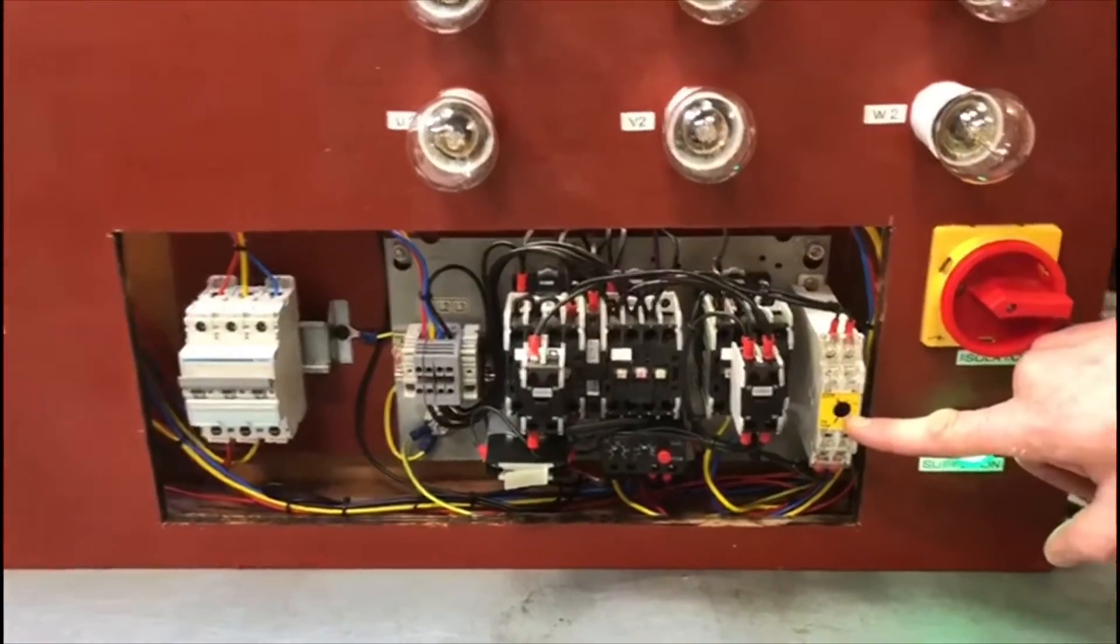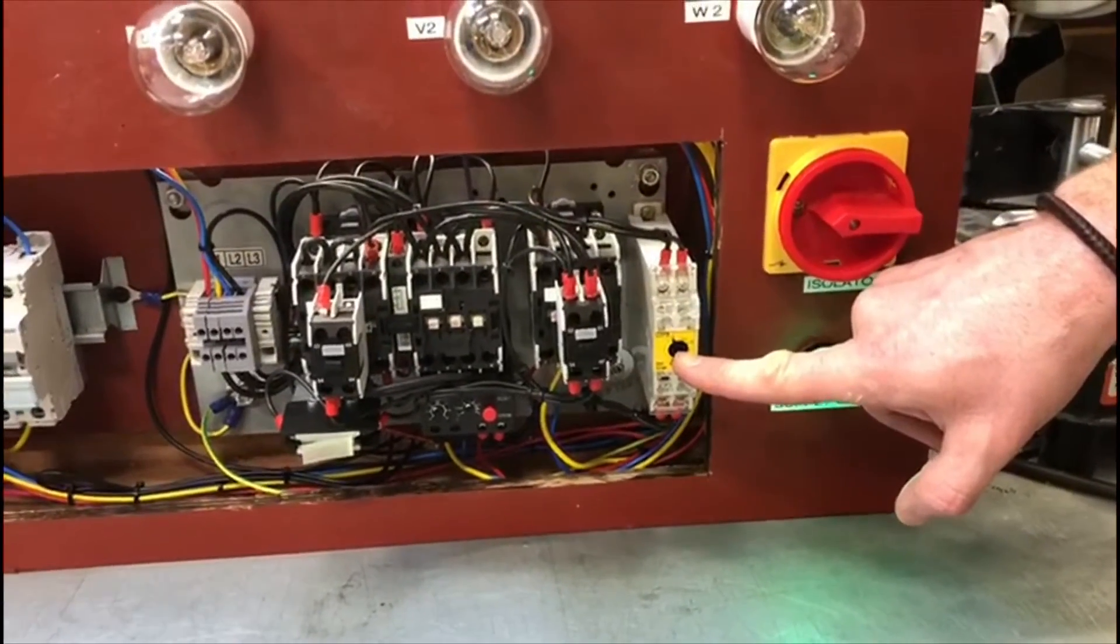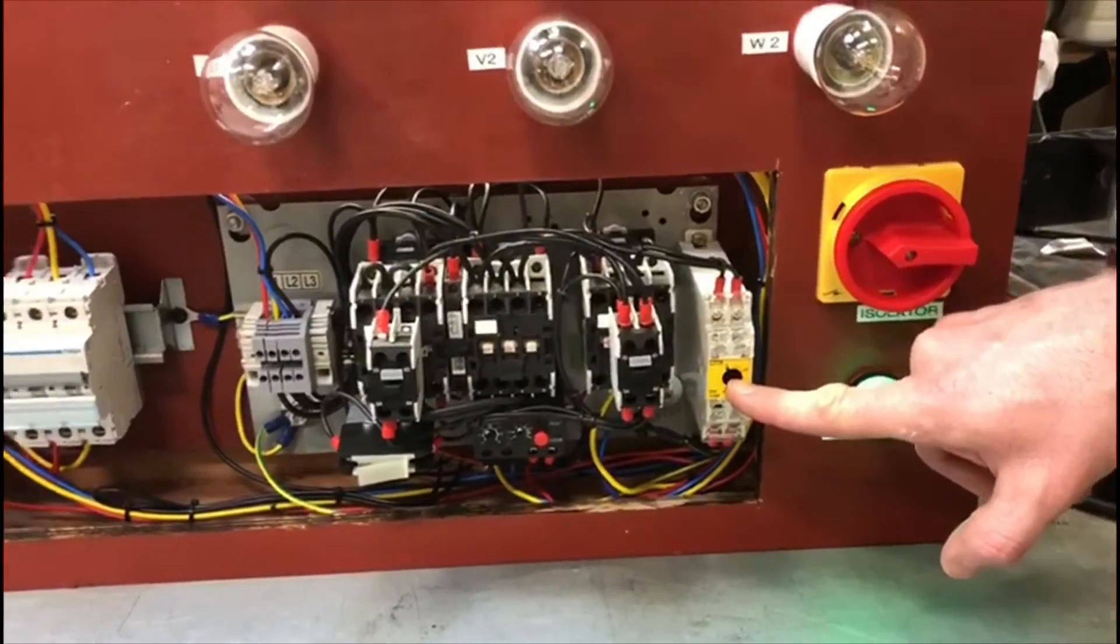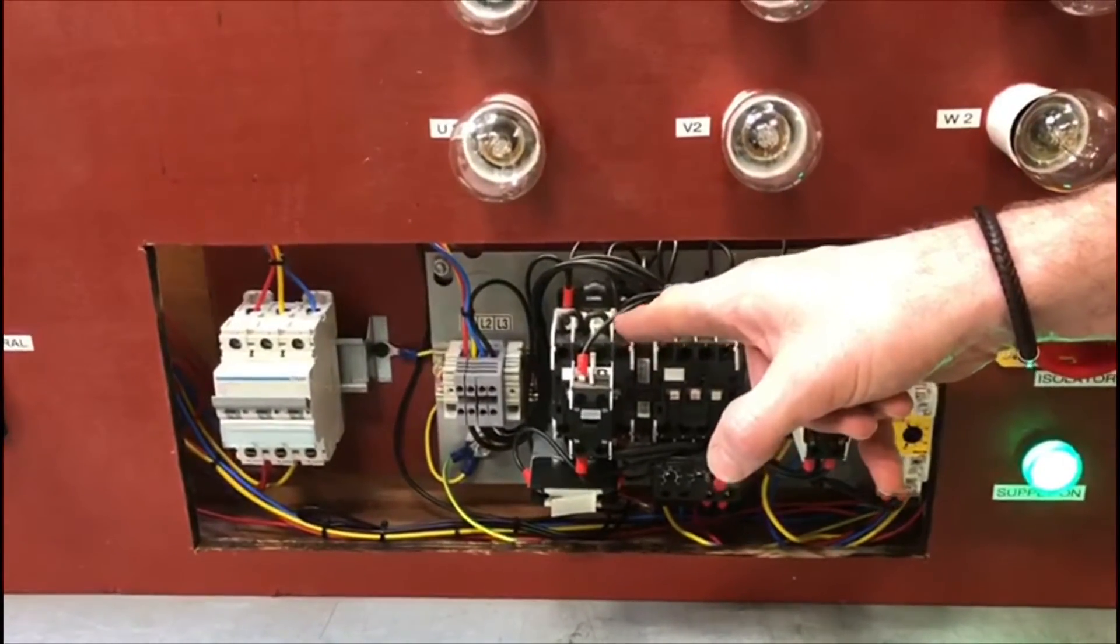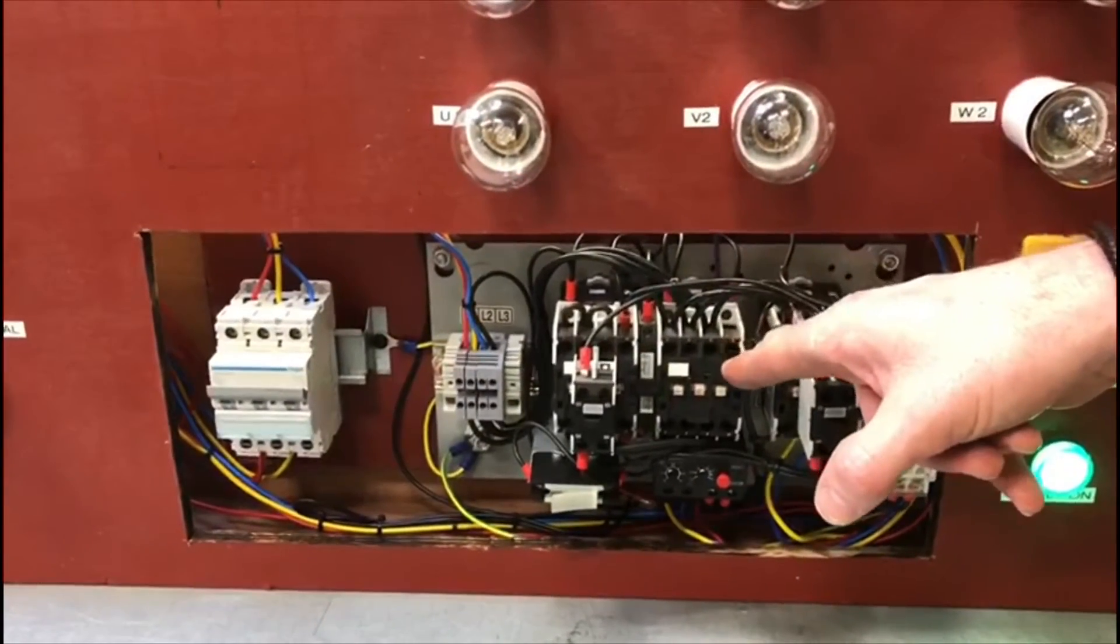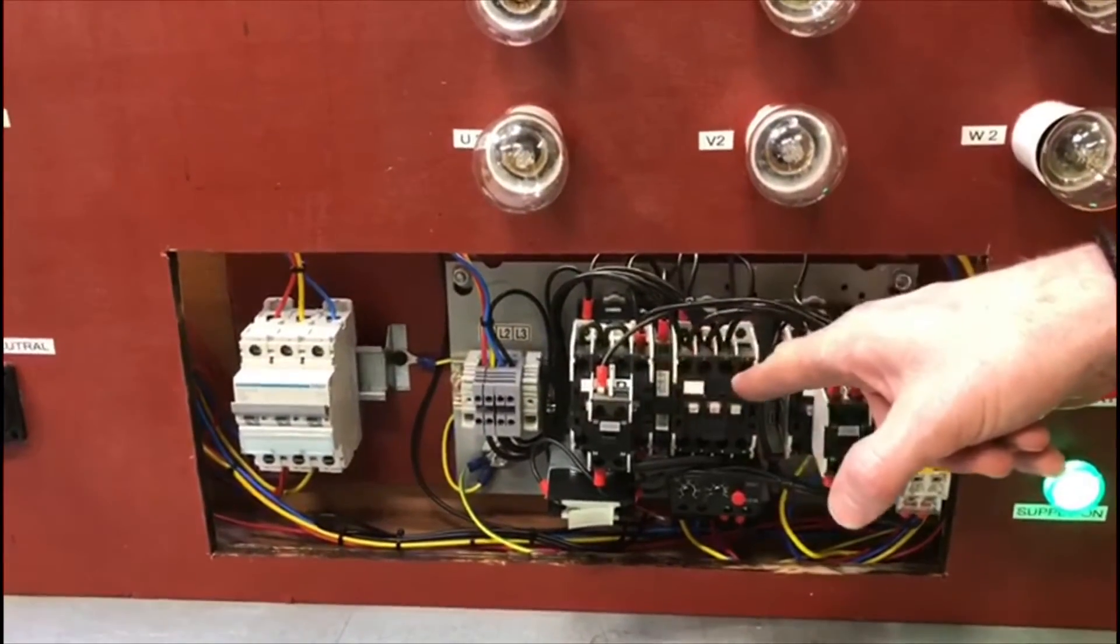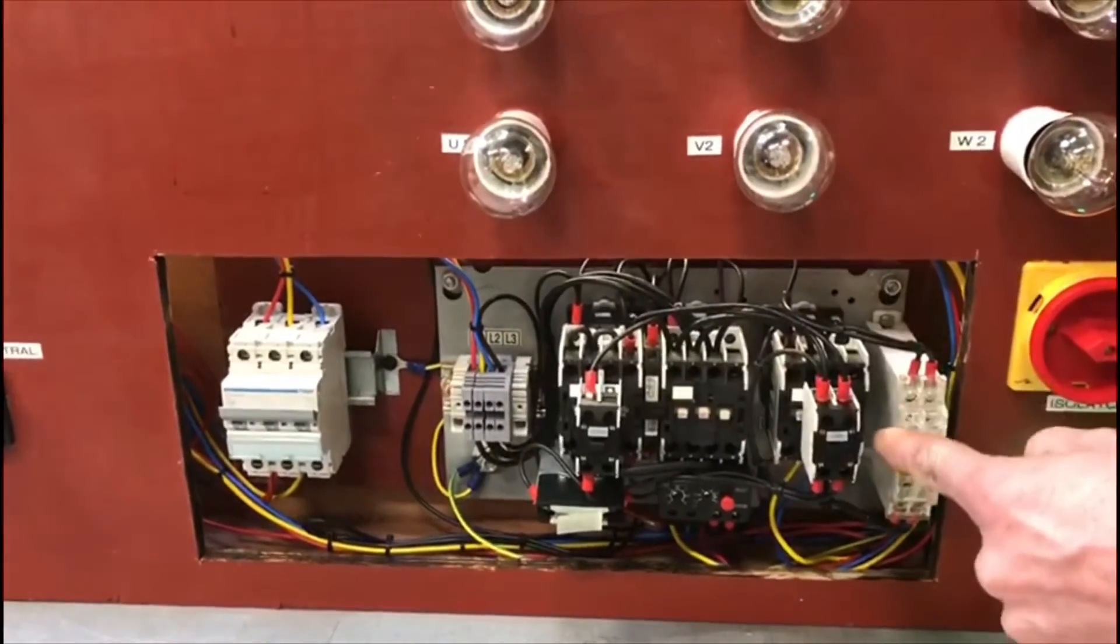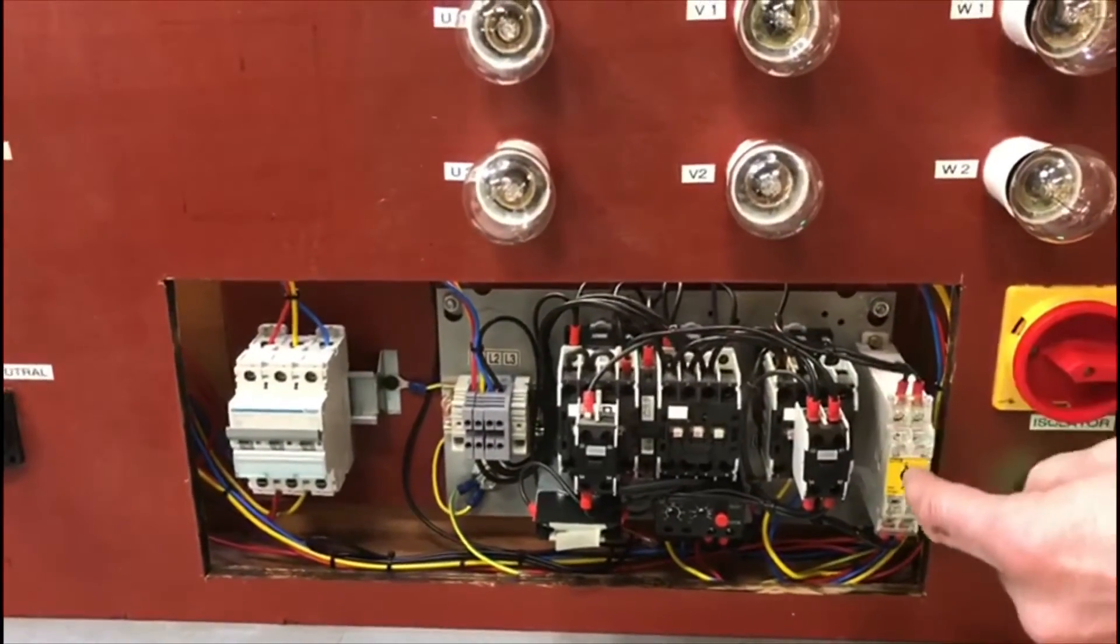After a duration, and I believe I've set this to about 20 seconds, this is the changeover time switch, so after about 20 seconds after starting it, this contactor will pull out and this contactor will pull in. So this being the star contactor, this one being the delta.